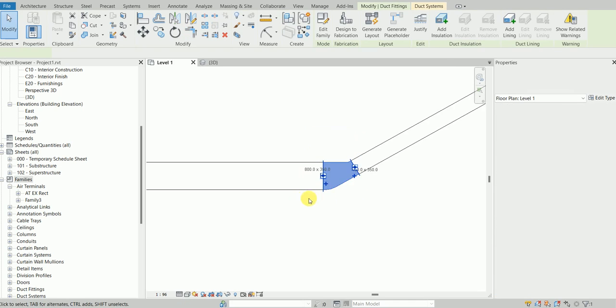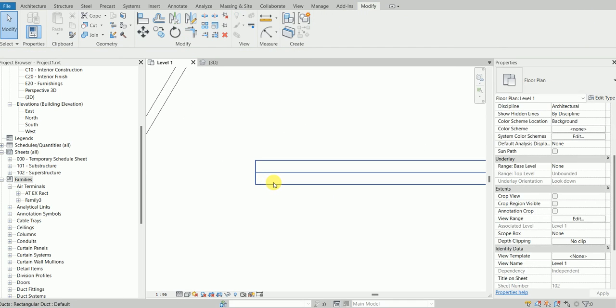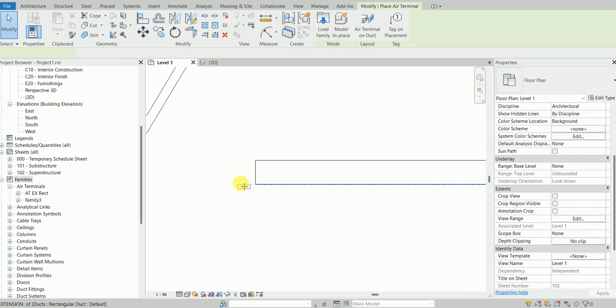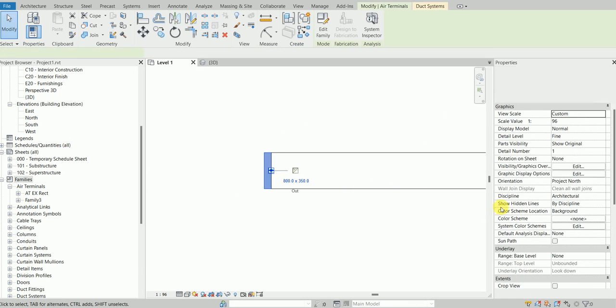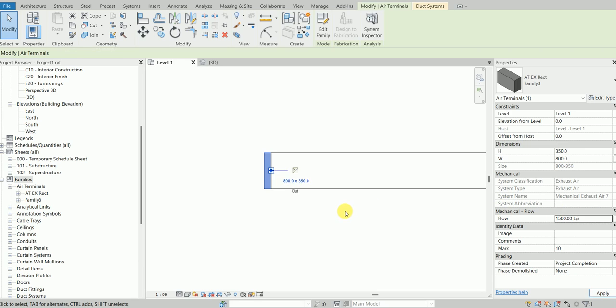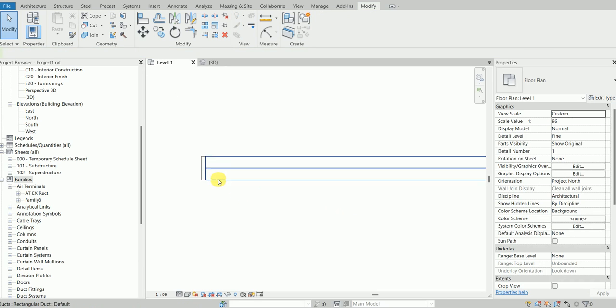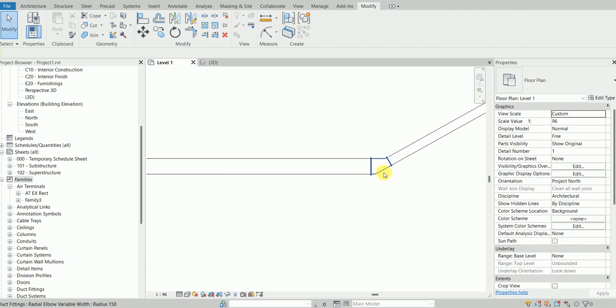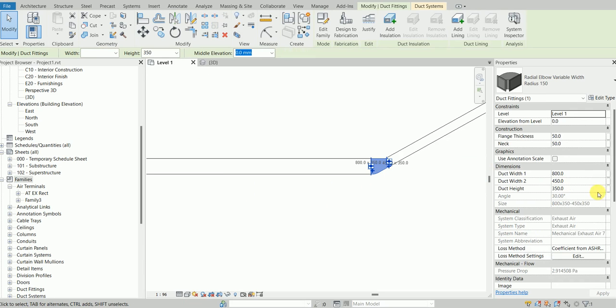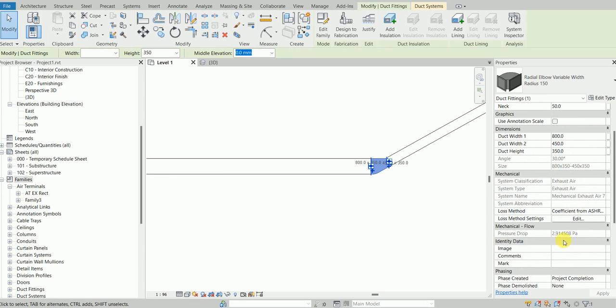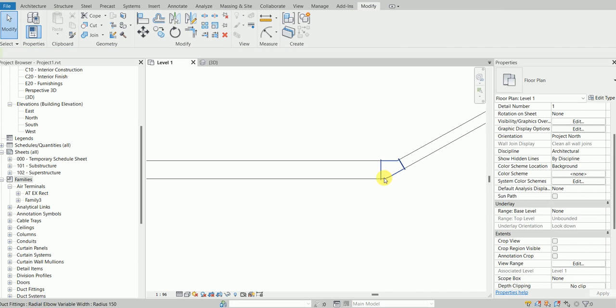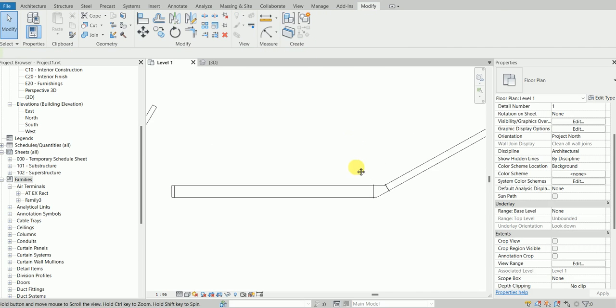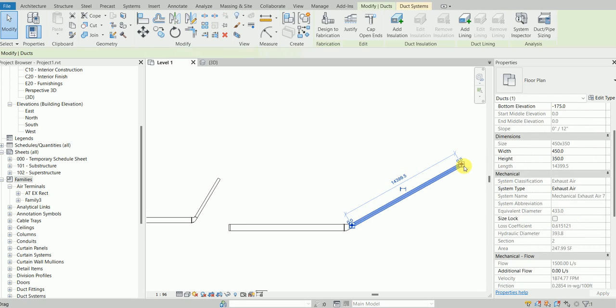I have this elbow, so I'm going to load an air terminal and set some value. Let's say 1500. With 1500 it's showing me the pressure drop of 2.91 pascals, probably because the angle is very less. I can even have an angle of 90 degrees, but let's first test this.